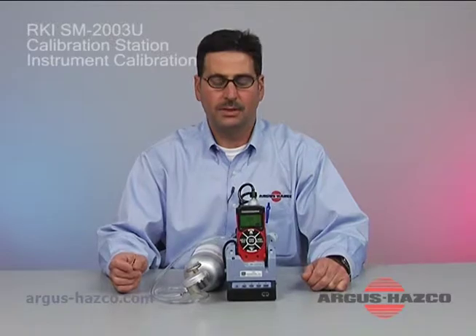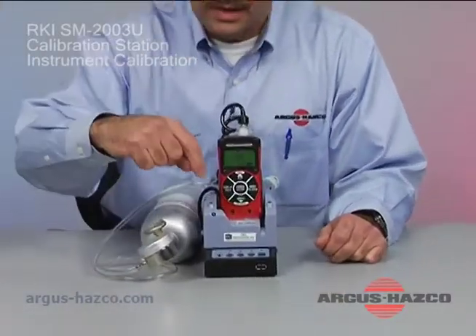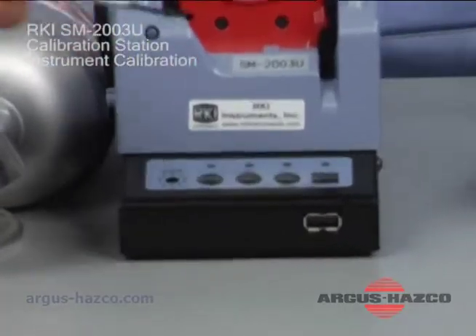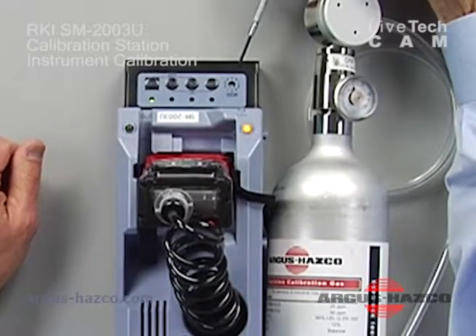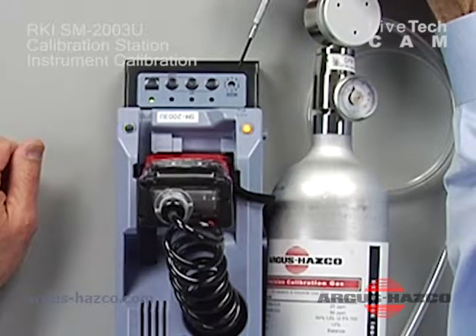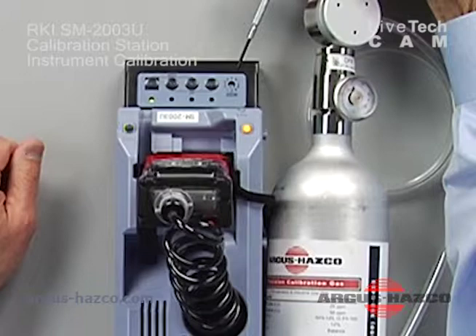Now we'll finish with the discussion of the buttons. Again, I mentioned them earlier, but I want to make sure that everybody understands the sequence of lights and what occurs when the unit is calibrating or bumping. Again, if you go from left to right, we're going to show the switch positions, and my preference would be to switch it to position 6. Again, that determines how long the air is going to be flowing to the unit to zero it, and how long the cal gas will be flowing to the instrument. And then, with position 6, if it fails to pass the bump, it immediately goes to calibration.